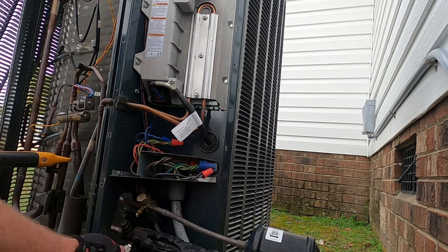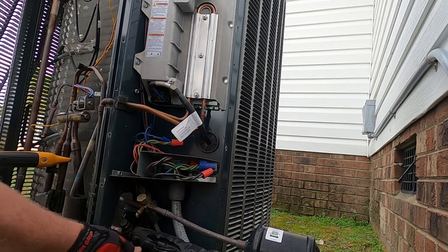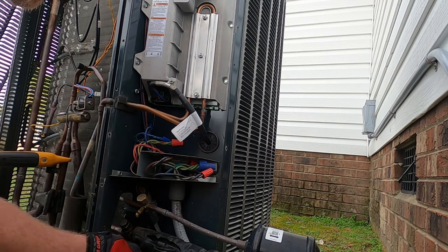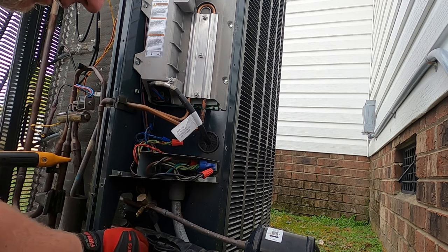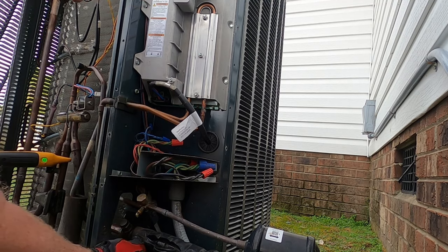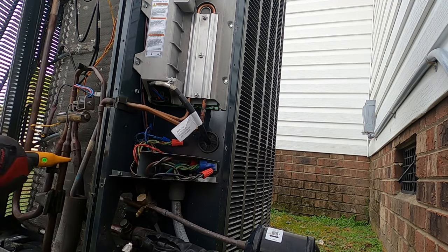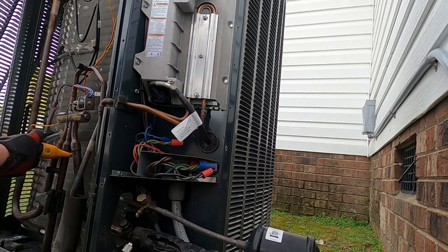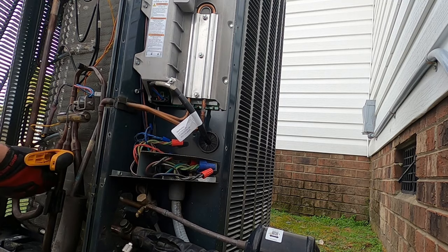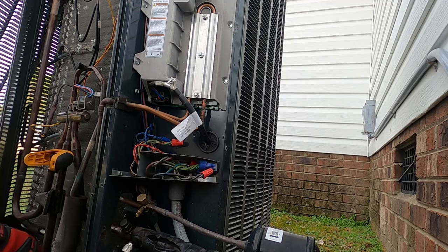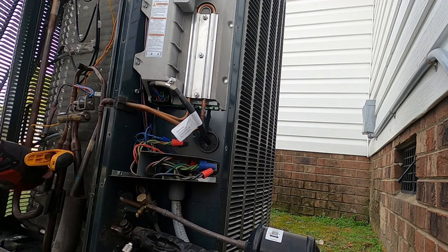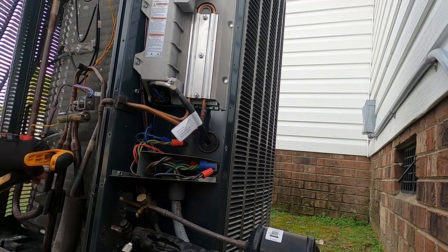Yeah, that's going to be my high side now. I'm probably going to have to replace that Schrader core, or tighten it or something. The charge is good. It probably didn't start leaking until I started messing with it. Let me get over here to my true suction, and we'll check the pressures. They're going to be a little high. Imagine running the heat when it's 70 or 68 degrees out here.